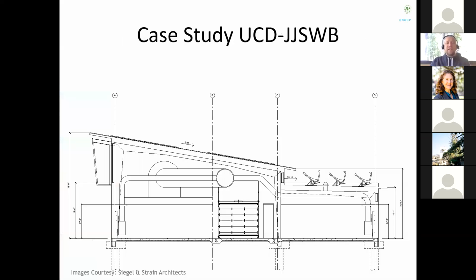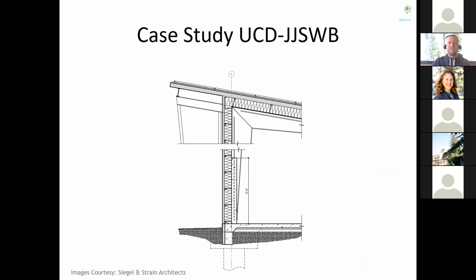Very simple building. It uses displacement ventilation, with no active heating or cooling system. It uses an ultra high performance envelope to maintain interior temperature, and night flush from the ventilation system to cool the building down at night naturally with outside air. We've also included thermal mass to get that lag.